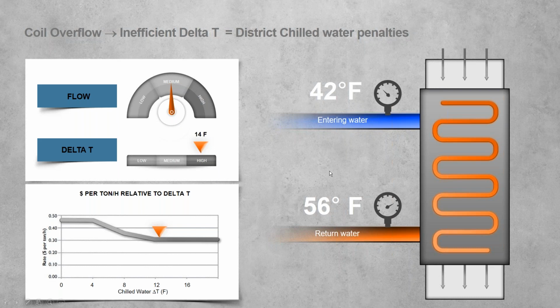What we know, as we mentioned before, is that systems and coils tend to overflow. So if we watch my graph up here on the top left, we'll see that as flow increases, this causes the coil to overflow and become inefficient, which means I lose my heat transfer. I don't have the same amount of time to take that heat transfer out of the air to water exchange. My delta T drops. In our example here, we went from 14 down to 4.